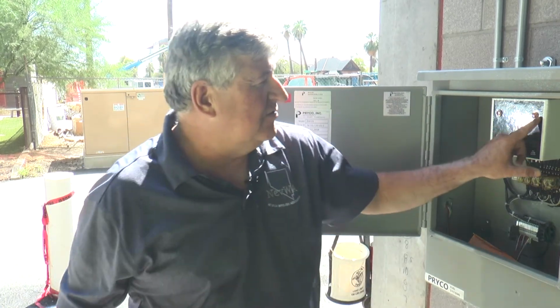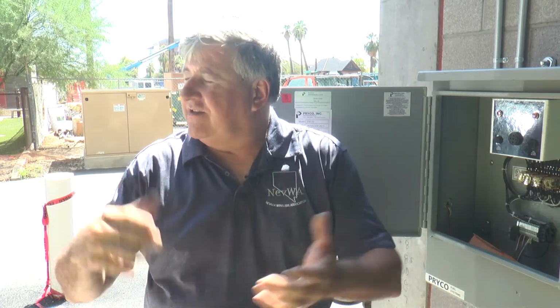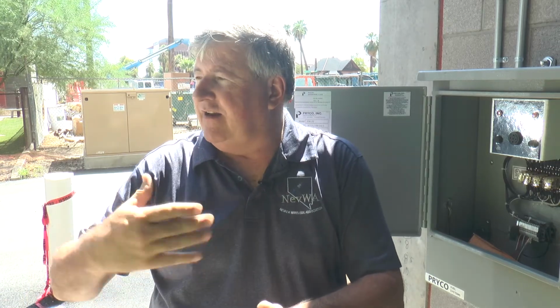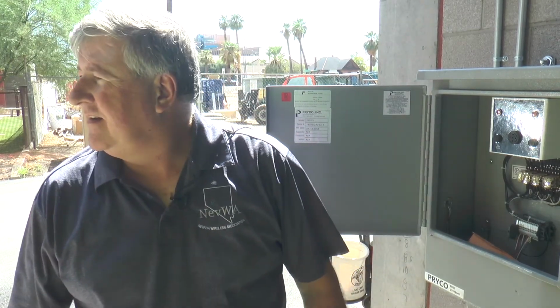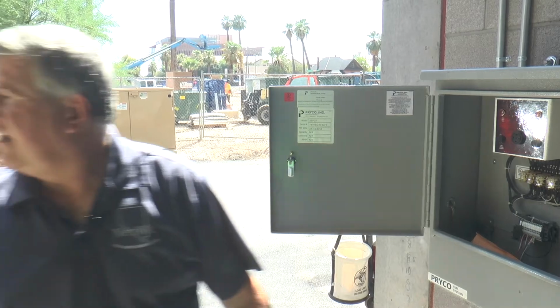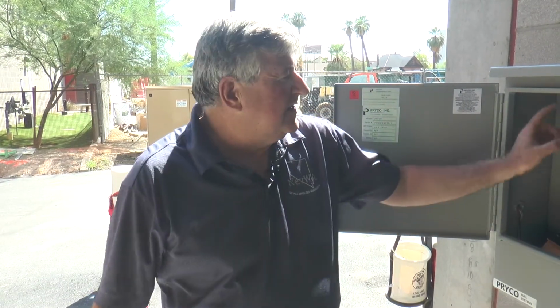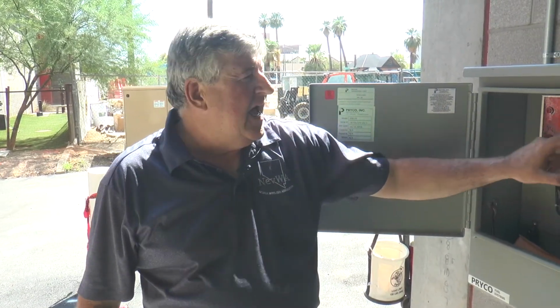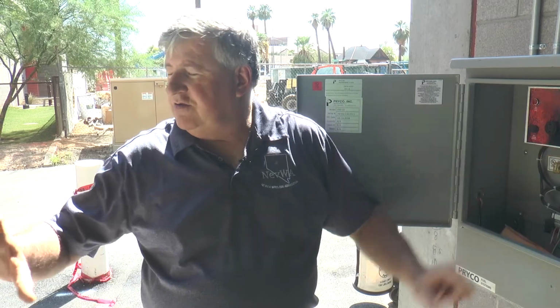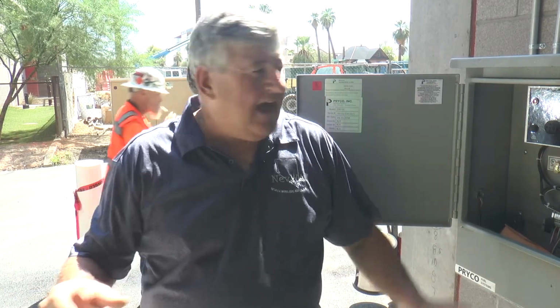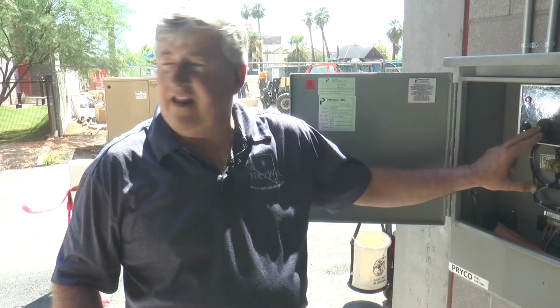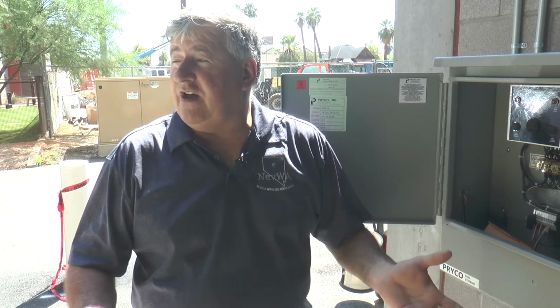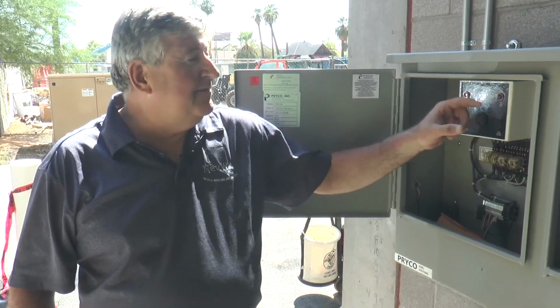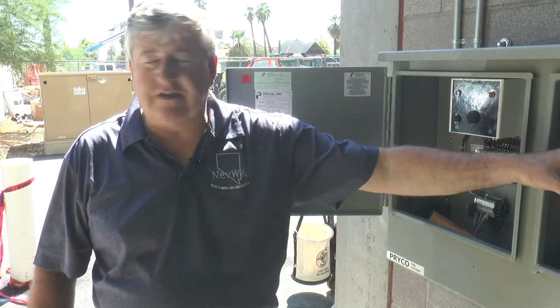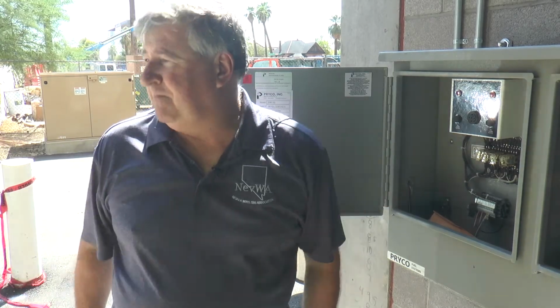So every time the solenoid valve opens and closes and it gets close to this alarm, it's going to cycle until the level goes down and the fuel empties out of the valve. Now, is this unit set for the 90%, so I know 90% fill? Yep, it's set for 90 right now, and 95 also. So there's 2 senders in the tank that will set off this light and alarm, letting him know that he's got to shut his fuel off. If he doesn't in time, it's going to just basically close the valve, cavitate his pump, and he's done.